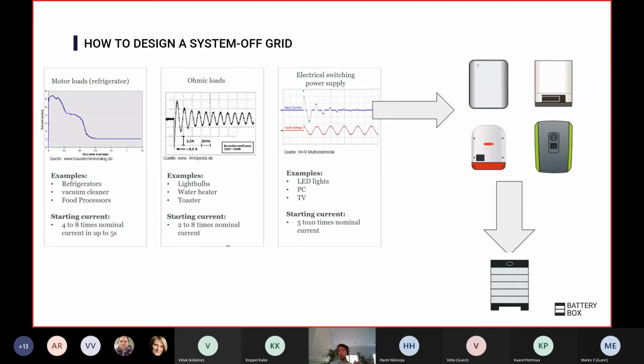For one or two seconds, you might have really big power surges. For example, when you switch on a pump, many people don't realize that for one or two seconds it will multiply the power by seven. So you need to size the energy storage system to support seven times the power of your load. That's why off-grid systems tend to be significantly oversized to withstand those power surges.